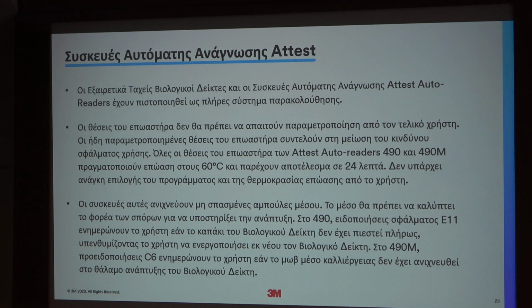So one other important thing should be the selection of the autoreader, because the autoreader should read what the biological indicator shows, but at the same time, it should prevent the risk of human error. What I mean by that is, if your autoreader requires many manipulations, like putting it in this well, changing the temperature, also selecting the right temperature, it means that it requires more information from your side, and this can be open to error. So any type of biological indicator plus autoreader should also provide some safety features.